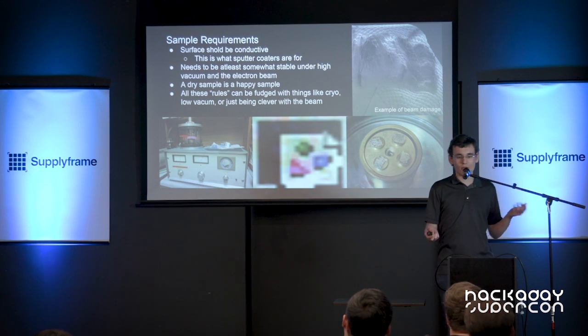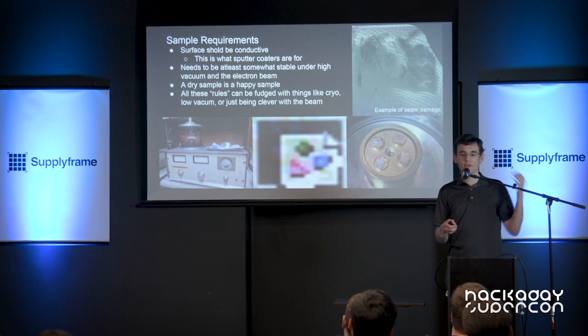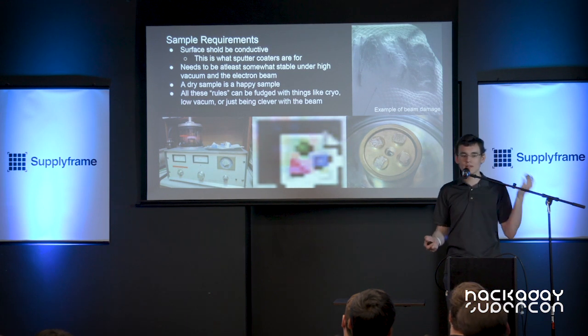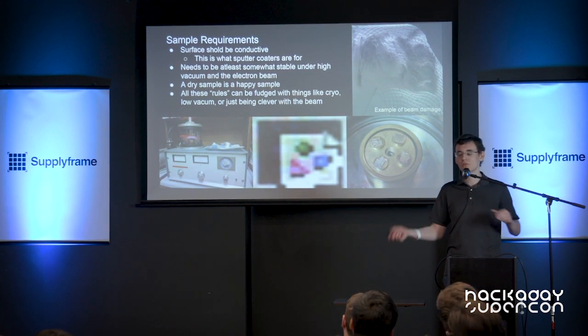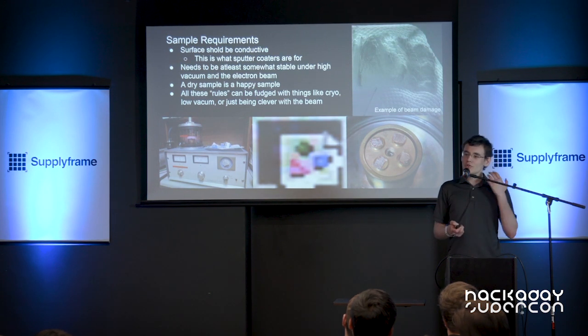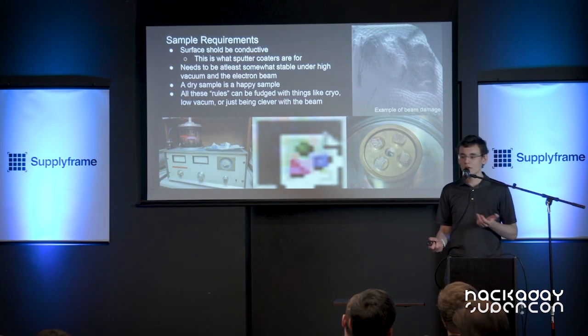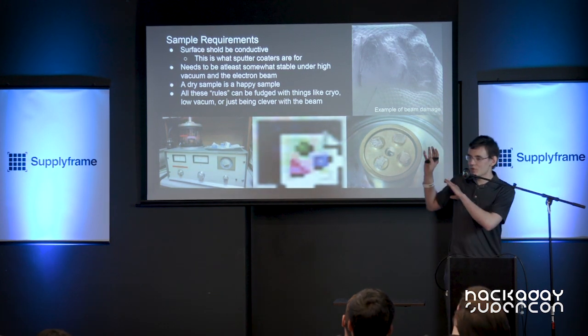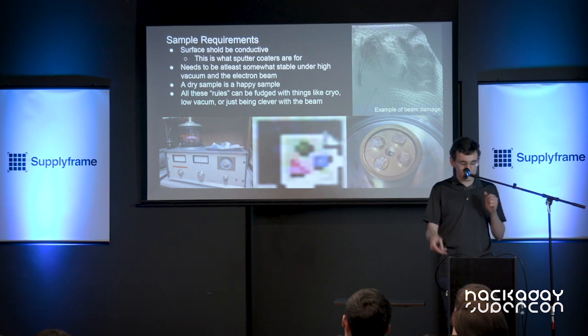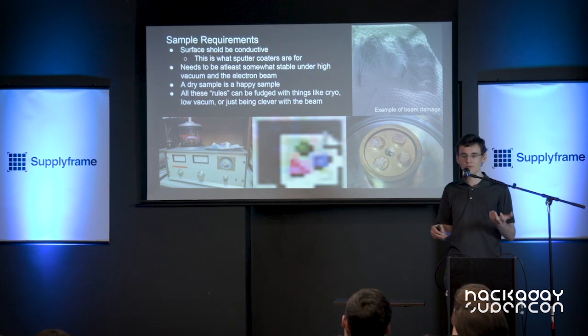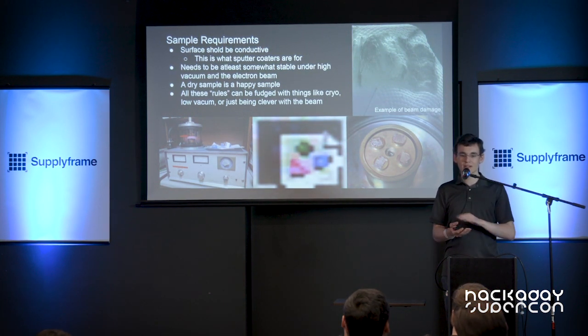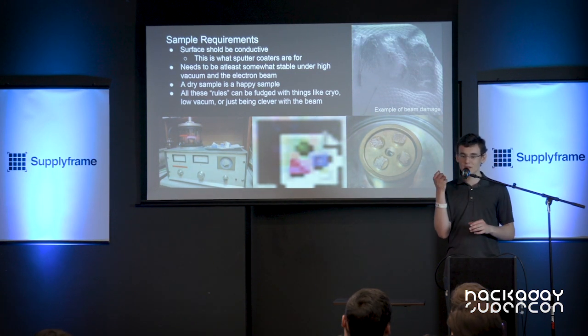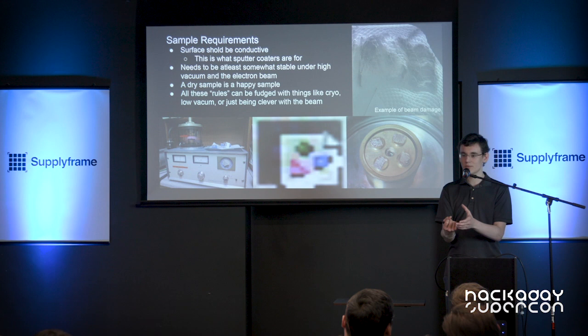A dry sample is a happy sample. In an electron microscope, the entire thing is held under a very, very high vacuum. Any moisture inside is going to want to escape, and that escaping moisture can cause problems in all sorts of ways. So you've got to dry it out somehow, being careful not to deform your sample too much. You can dry it using things like a critical point dryer, or literally just freezing it and letting it sublimate out really slowly. There are also things like cryo-SEM, where you literally keep everything inside the microscope at liquid nitrogen temperatures — when water's at liquid nitrogen temperatures, it actually doesn't sublimate nearly as fast. So you can maintain a piece of ice held with liquid nitrogen inside of a high vacuum chamber.